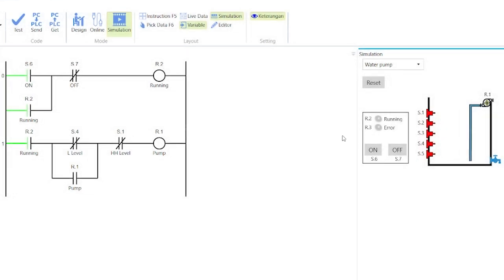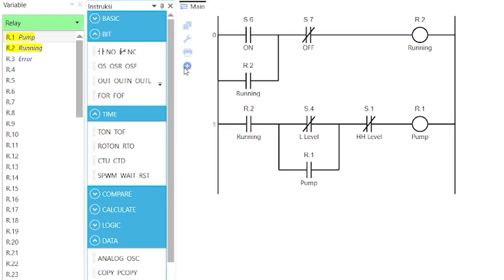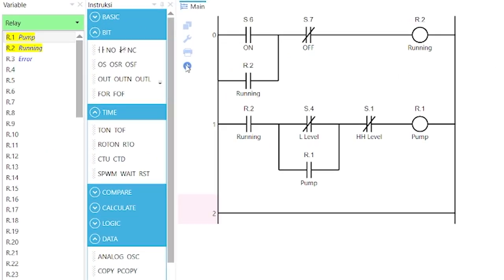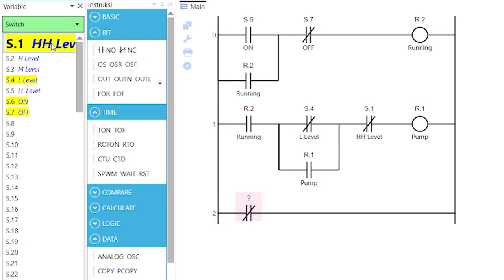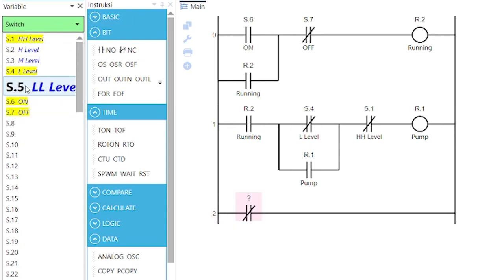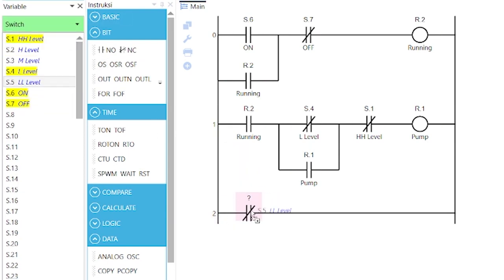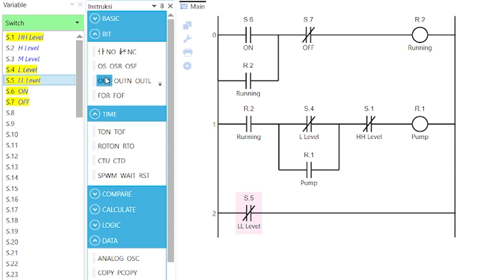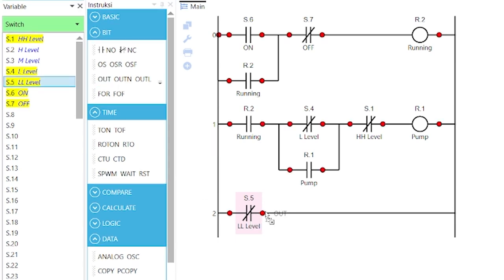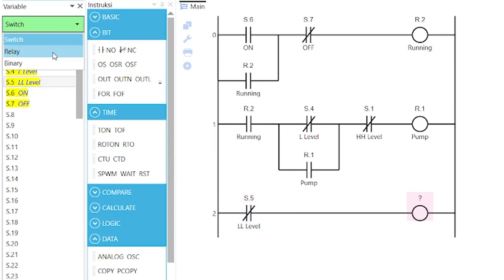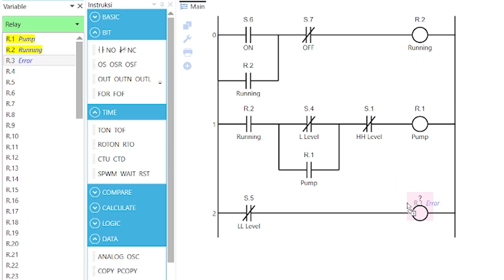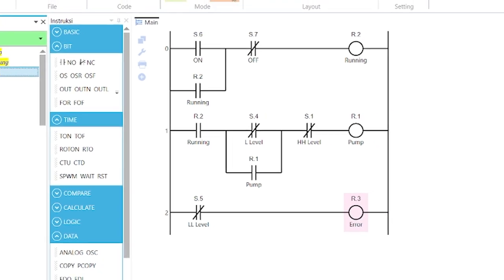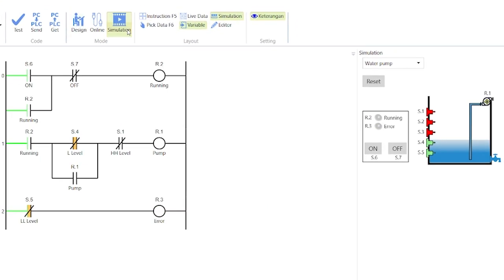Finally, to show the error indication, add another rung. Add to the rung a normally closed contact with variable S.5 for the lowest level switch, and a coil with variable R.3 for the error indication. Then, simulate the program.